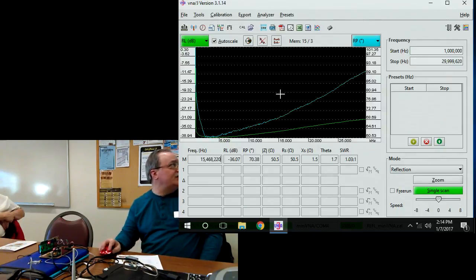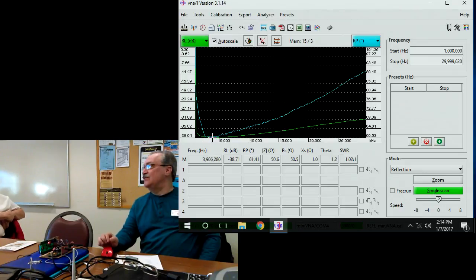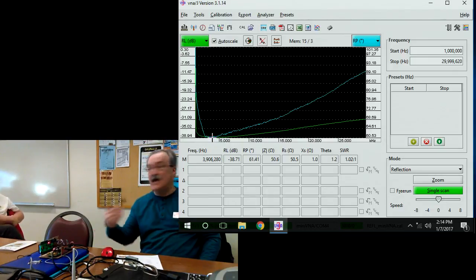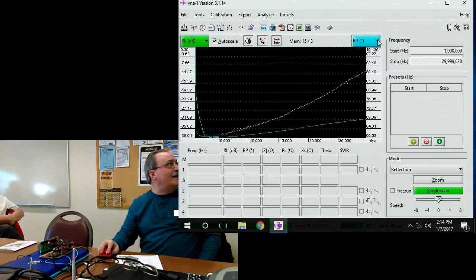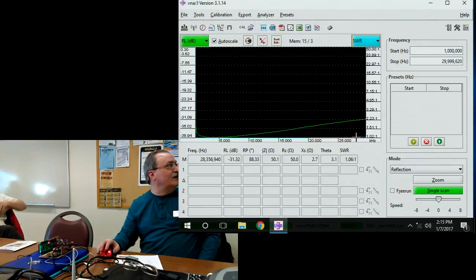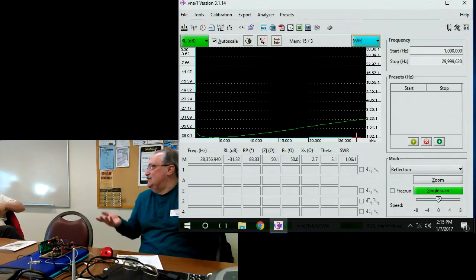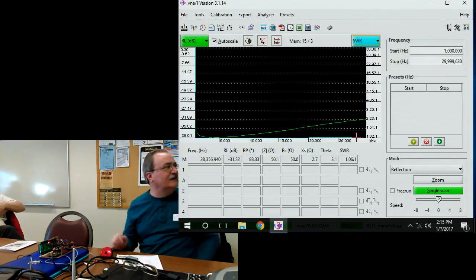Okay, so what that shows us is it shows us the return loss in decibels. So right here is going to be where our best standing wave ratio is going to be, because that's where the least loss is seen reflected back. If I put SWR on there with the blue trace, then it's down here, and we're essentially under 1.02, 1.06 to 1 across, which is what you'd expect with a 50 ohm resistive load.